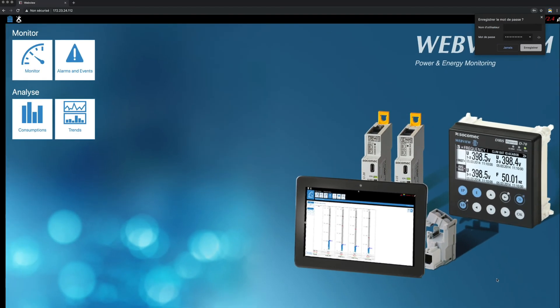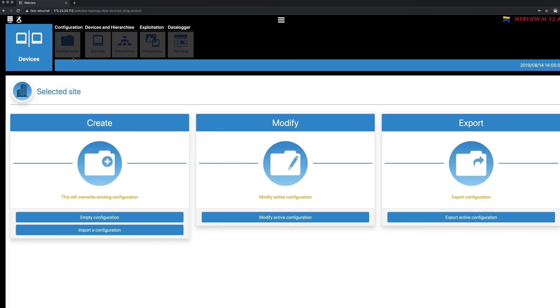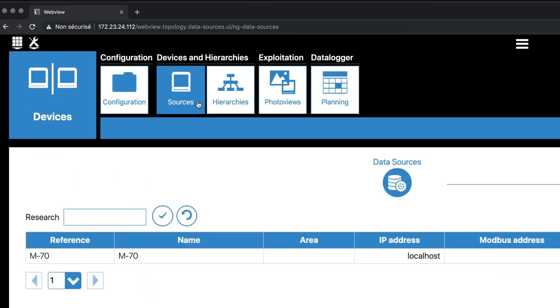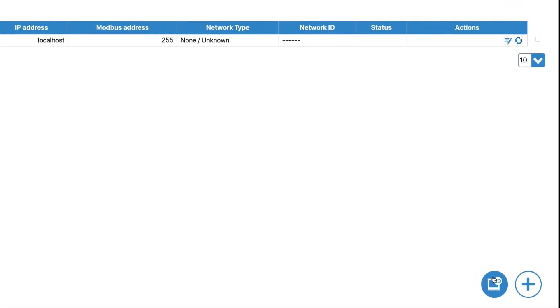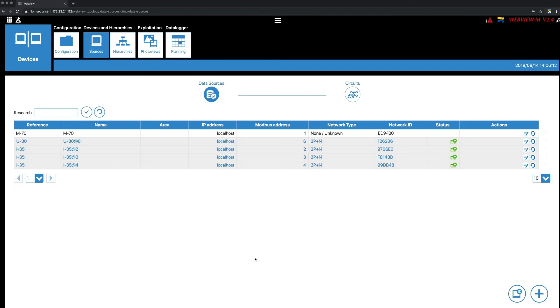Once connected as admin, click on the wrench icon in the top left corner, then click on Devices. Click on Modify Active Configuration, then Sources. From the Data Source tab, click on the Scan button to add products present in the M70 display topology. Once products are added, you can change their names and sort them by location. The Plus button allows you to add products manually to the topology, whether they are locally connected to the M70 via the DigiWare or RS-485 bus or remote via Ethernet.